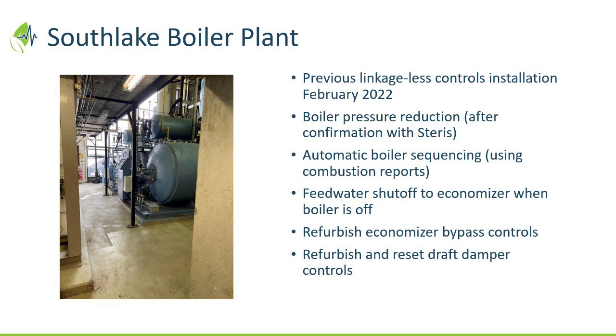Yeah, been there, done that. I agree with what you're saying. We've done a lot of work with linkages when we went that route, and I think the key with that is having the proper setup, for sure, 100%. And I do a lot of that with my subcontractors. They come in once every 6-7 months, and we just check to make sure that the fuel is proper and it's doing what it needs to do. But Ian, you're right. We've done it. It works. We have old boilers, so it's been working pretty good so far.